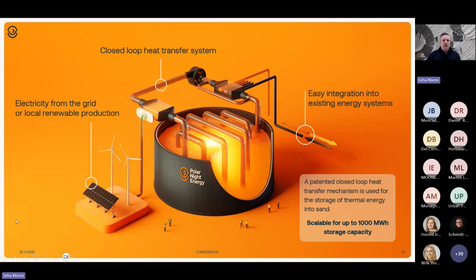This is a simplified illustration of the sand battery and how it works. We have our supply from renewables, and the sand battery consists of three main components: a resistor, a blower, and a heat exchanger, connected to each other with a closed loop piping system. We heat up clean air to 650 degrees and transfer the heat via this piping system into the sand in the storage tank. On the other side, we can discharge the energy with a heat exchanger or a steam generator for an industrial process.